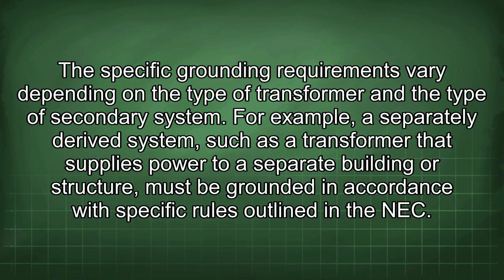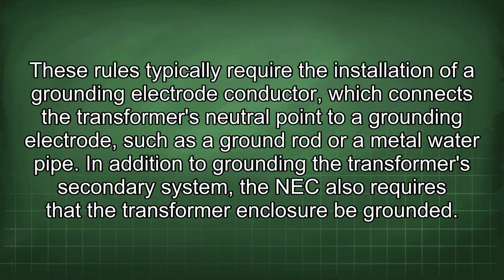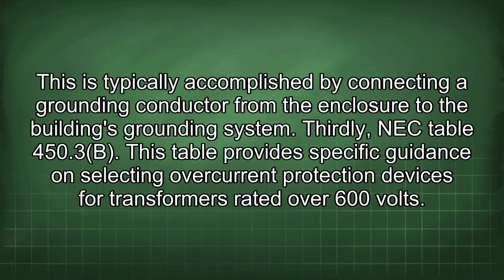The specific grounding requirements vary depending on the type of transformer and the type of secondary system. For example, a separately derived system, such as a transformer that supplies power to a separate building or structure, must be grounded in accordance with specific rules outlined in the NEC. These rules typically require the installation of a grounding electrode conductor which connects the transformer's neutral point to a grounding electrode, such as a ground rod or a metal water pipe. In addition to grounding the transformer's secondary system, the NEC also requires that the transformer enclosure be grounded. This is typically accomplished by connecting a grounding conductor from the enclosure to the building's grounding system.